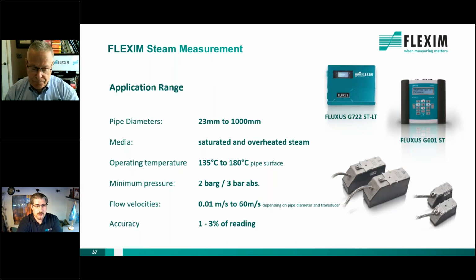Okay, so just quickly, the main specifications for where you can measure steam. Basically, the pipe diameter range starts at 23 millimeters up to 1,000. It is for saturated and overheated steam, although we like to have dry steam actually. And the operating temperature that you need for our transducers is 135 to 180 degrees C. This is because we need a certain minimum pressure to be able to set up a gas measurement, and this is 2 bar G or 3 bar absolute. This accordingly corresponds to a saturated steam temperature of 135, and 180 max, because this is what the transducer can stand. For the flow velocities, we can go as high as 60 meters per second. So this is very much enough for most applications, as you like to have something between 20 and maximum 30 meters per second in your steam applications. You shouldn't go higher than that.